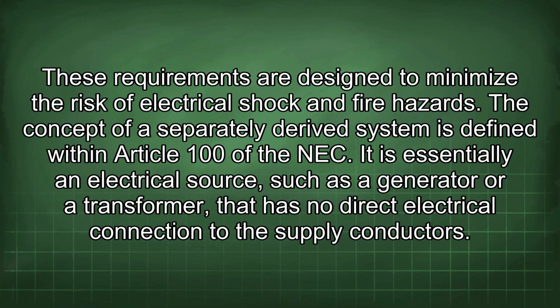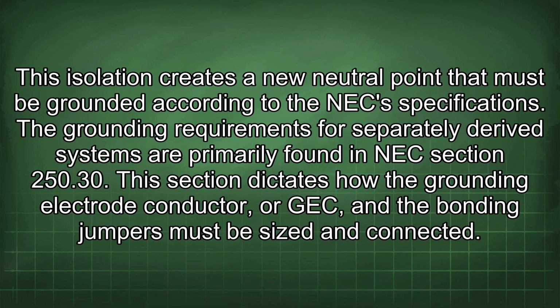The concept of a separately derived system is defined within Article 100 of the NEC. It is essentially an electrical source, such as a generator or a transformer, that has no direct electrical connection to the supply conductors. This isolation creates a new neutral point that must be grounded according to the NEC specifications. The grounding requirements for separately derived systems are primarily found in NEC section 250.30. This section dictates how the grounding electrode conductor, or GEC, and the bonding jumpers must be sized and connected.